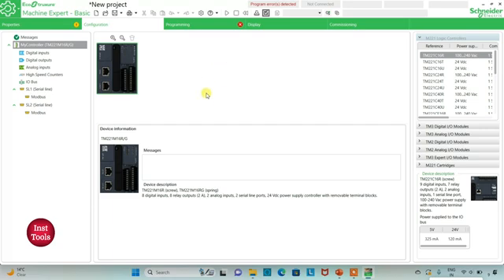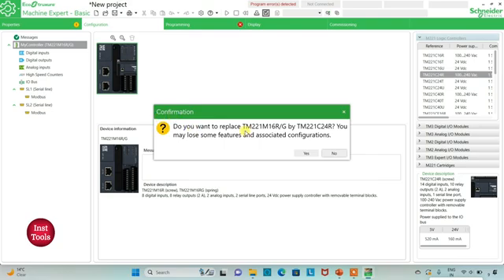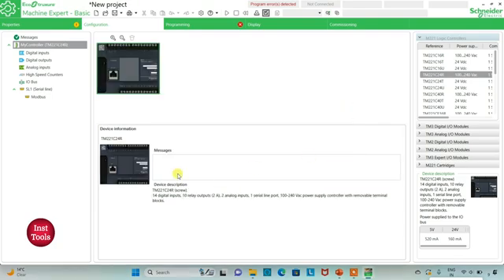In the configuration tab I need to select the logic controller. From the list of different logic controllers I will be using TM221 C24R — I will click on it and drag it here. I confirm replacing the previous controller. The TM221 C24R has 14 digital inputs, 10 relay outputs, two analog inputs, one serial line port, and a 100 to 240 volt AC power supply with removable terminal blocks.